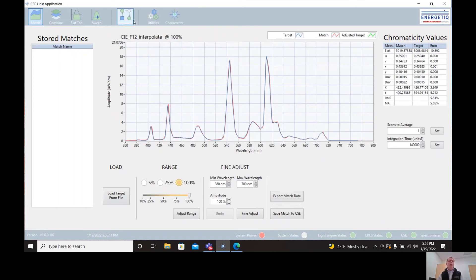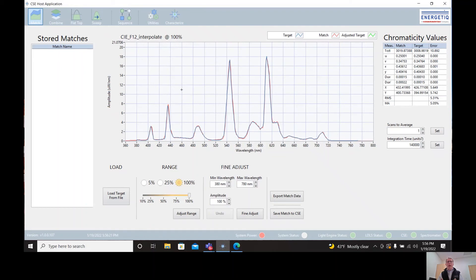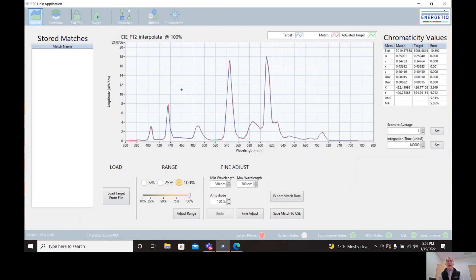Then there's a sequence mode here. Sequence allows us to take a number of spectra, target spectra that we've refined and we have just the way we like them, and define them as a sequence. And that sequence can be loaded onto the CSE and then triggered using TTL triggering very quickly to go from one spectrum to the next, typically within 100 milliseconds. And there's basically no settling time when you go from one spectrum to the next. So very fast steps from one spectrum to the next.